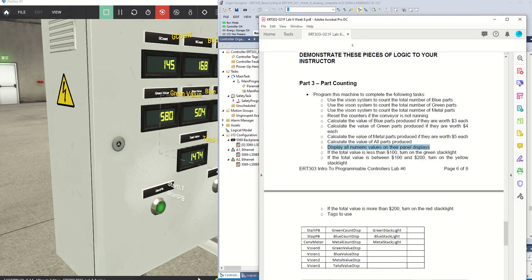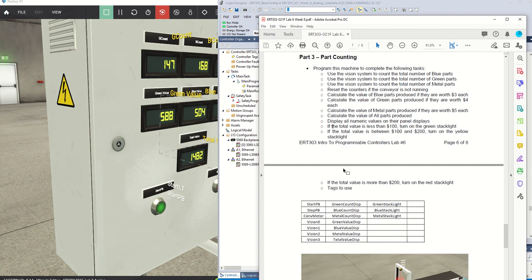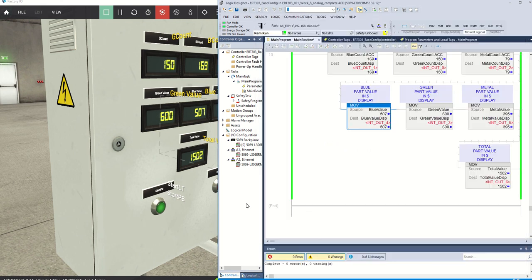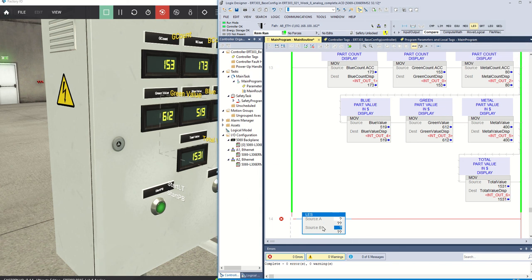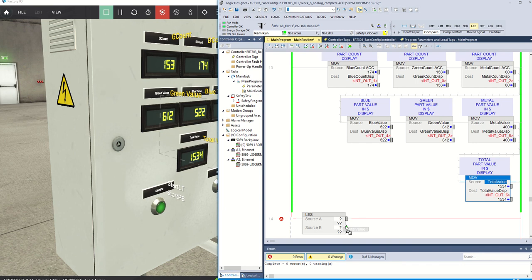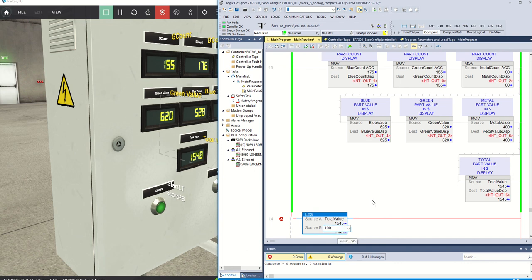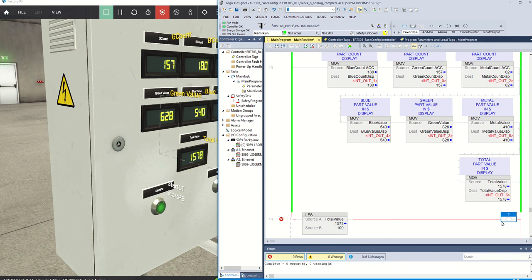Our final thing is to do a couple of comparisons. If the total value is less than $100, turn on the green stack light. We'll use the compare instruction set — specifically a less than instruction. Source A is total value, source B is 100. If this is true, we get an output to the green stack light. I'll duplicate this two more times for yellow and red.